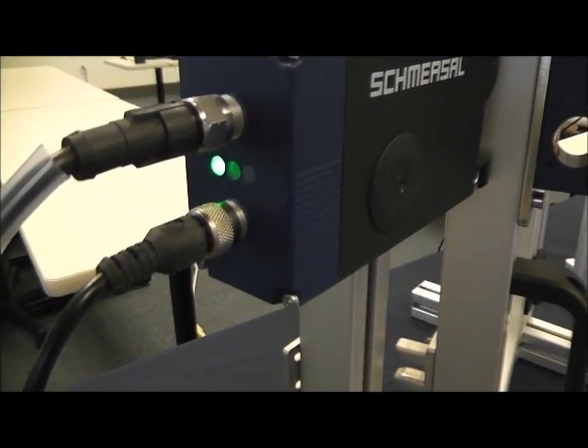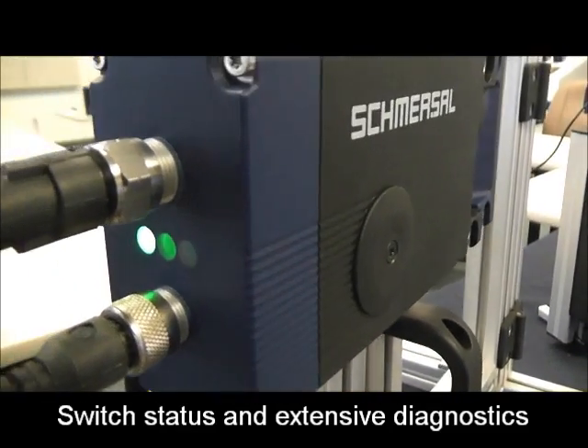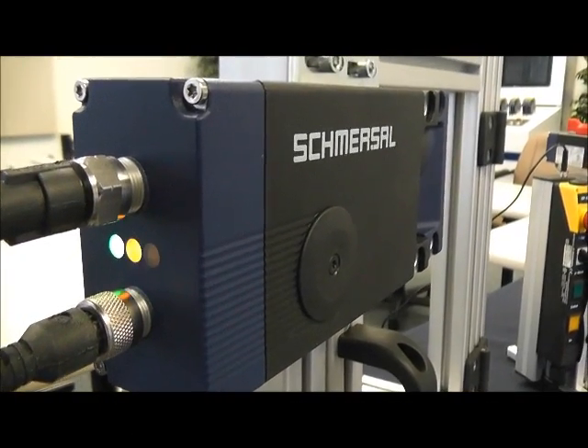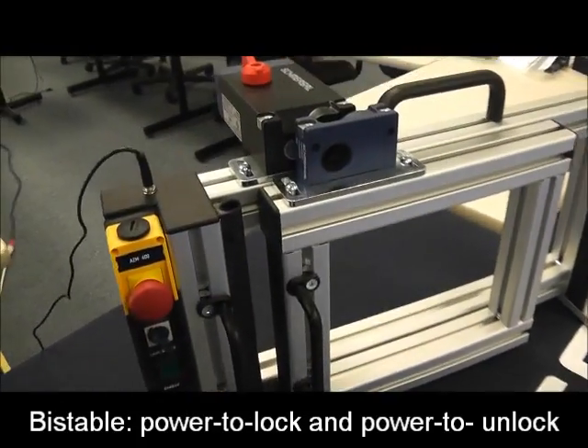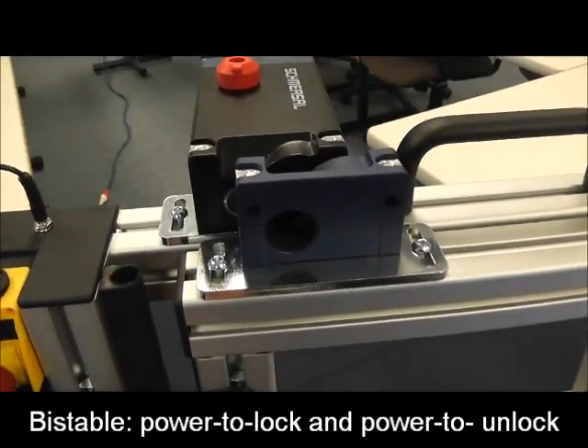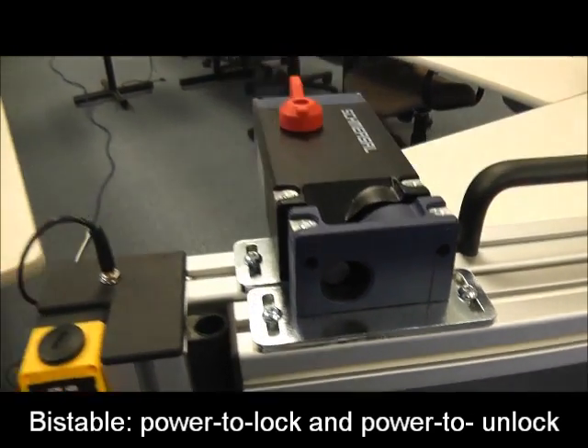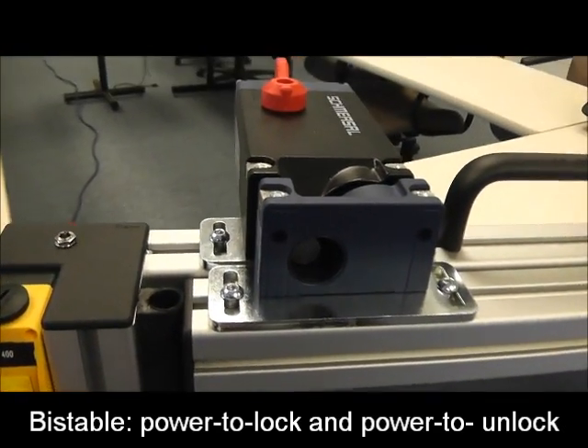If we look at the LEDs, we get errors and statuses of the switch. A blinking LED means that the door is closed. A solid LED means that the gate is locked. It is a bi-stable switch, so right now our switch is locked. And if we remove power, our switch remains locked.